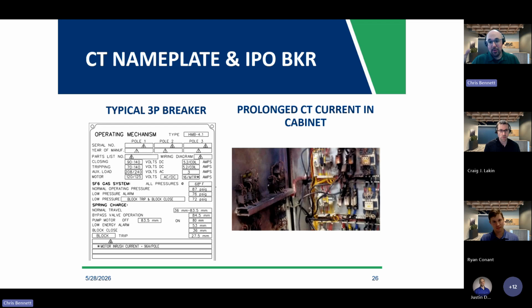Just to highlight that, typical 3-pole independent operation breaker nameplate on the left there, you will have 5.2 amps of DC current per coil. In this case, you will have over 15 amps of DC current flowing through that circuit back into your control house and back out to the breaker, because that is where the protective relays lie. Not exactly the safest thing.